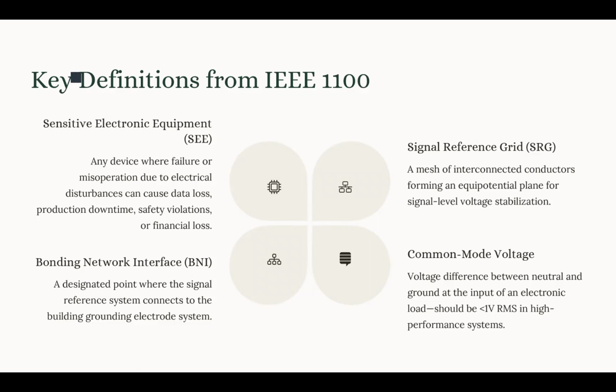Another definition that we have to mention is the signal reference grid, which we call SRG. The SRG is a mesh of interconnected conductors, normally copper strips, that forms an equipotential reference plane. The material of these SRGs is normally copper, with a typical spacing of 0.5 to 2 meters apart, which forms a grid pattern beneath our equipment. The target impedance is less than 1 milliohm at radio frequencies, at or around 10 megahertz.